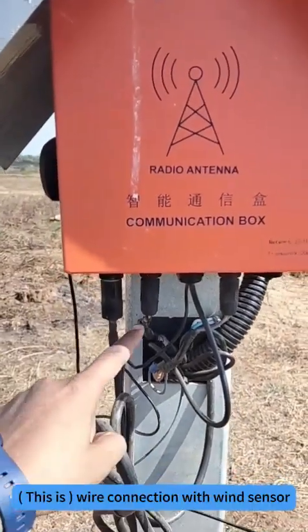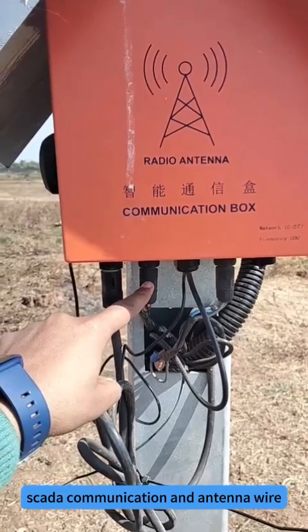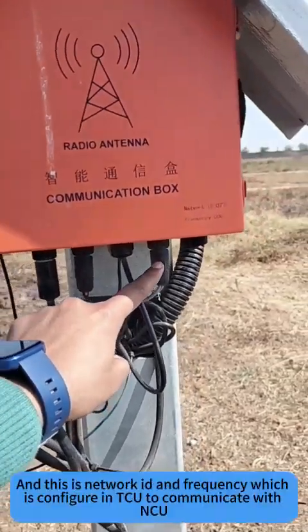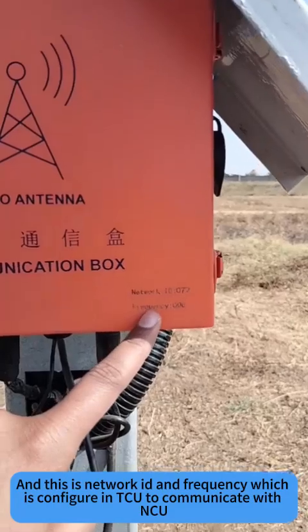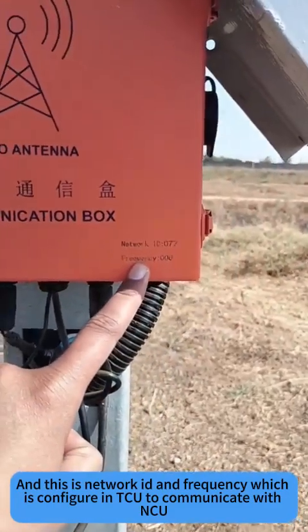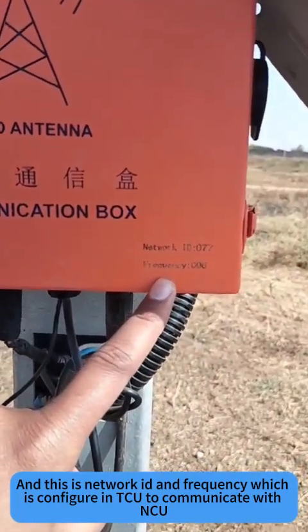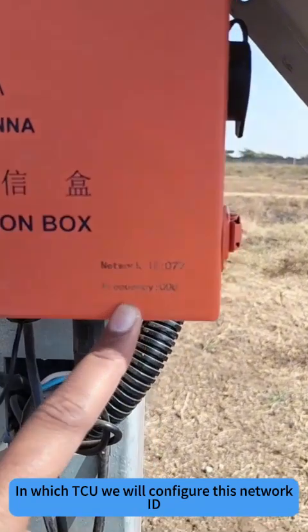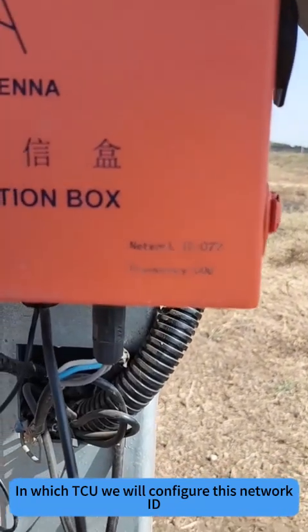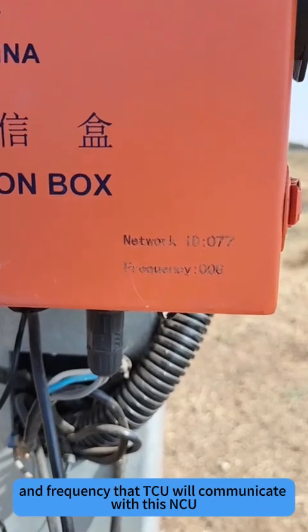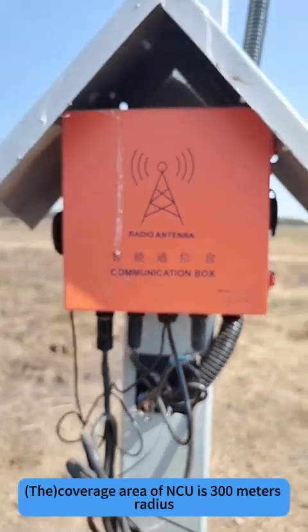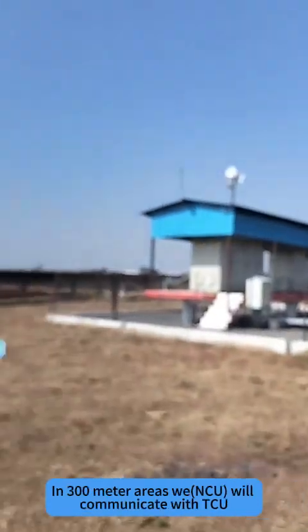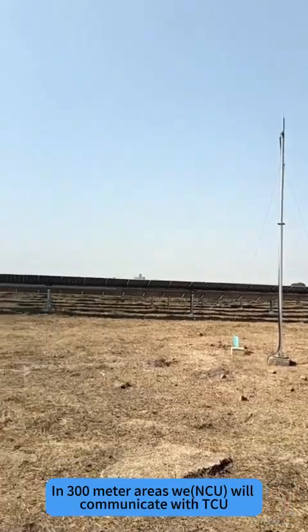Here are the connections: wind sensor, SCADA communication and antenna, power, and this is the network ID and frequency which is configured in the TCU to communicate with the NCU. Whichever TCU we configure with this network ID and frequency, that TCU will communicate with this NCU. The coverage area of the NCU is 300 meters. In a 300 meter radius it will communicate with all TCUs.